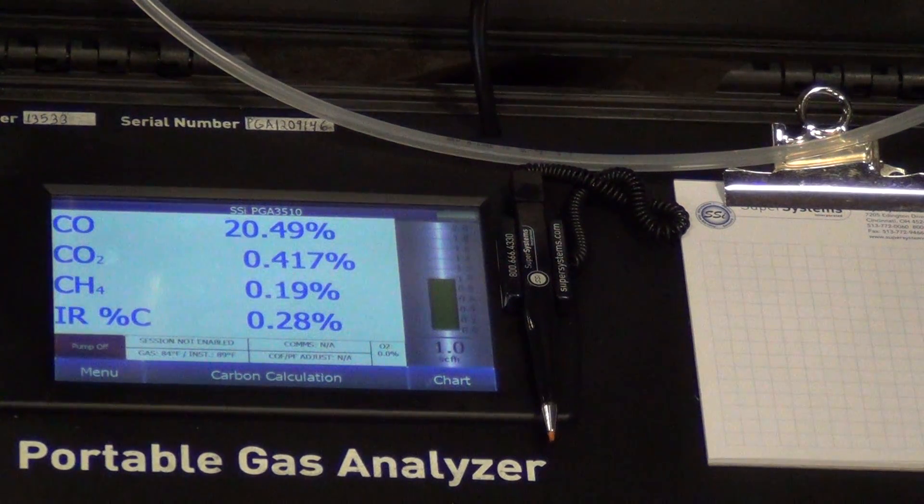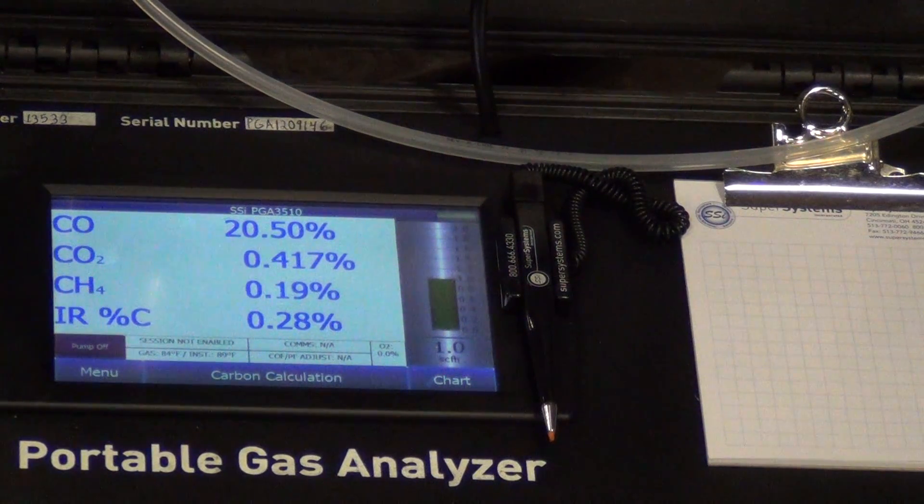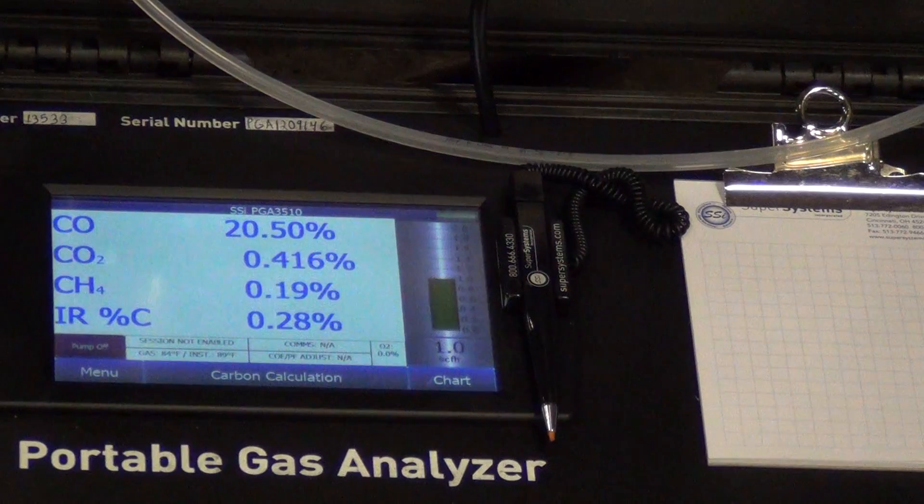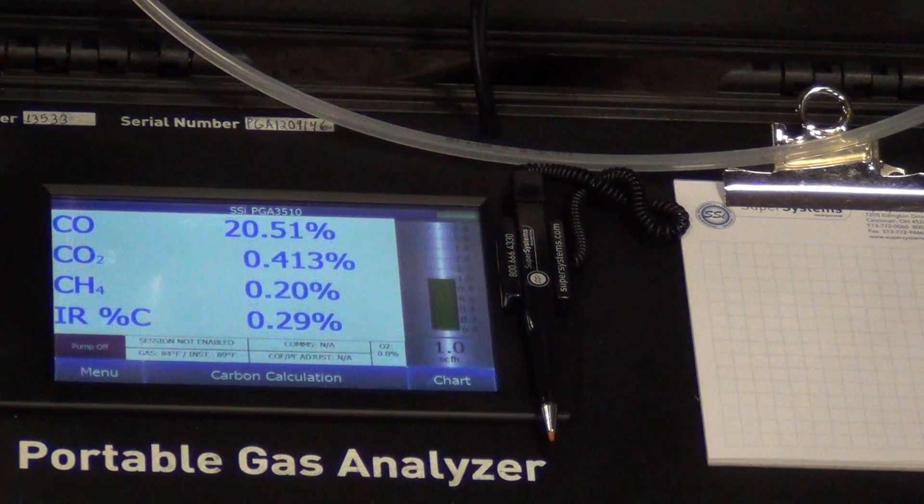Now as you get lower dew point or higher, they tend not to agree as much. Like a 20 dew point might be reading a 0.12 CO2. But around 40 dew point, you typically get a 0.35, 0.45 CO2.